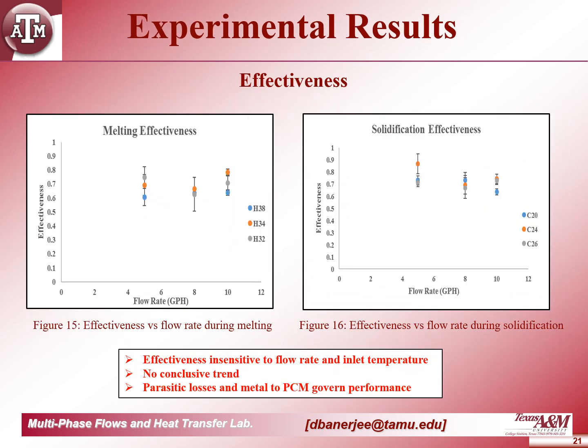The effectiveness of the Chevron plate heat exchanger is predominantly in the range of 0.6 to 0.8. Also, the effectiveness of the Chevron plate heat exchanger is invariant with inlet flow rate and temperature.